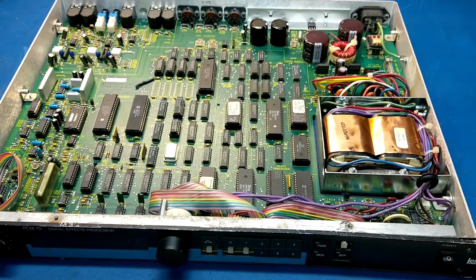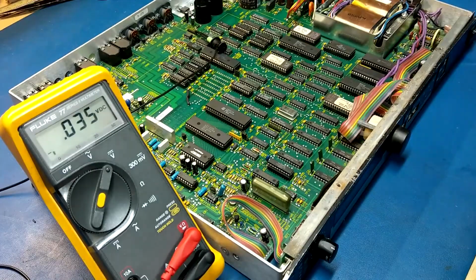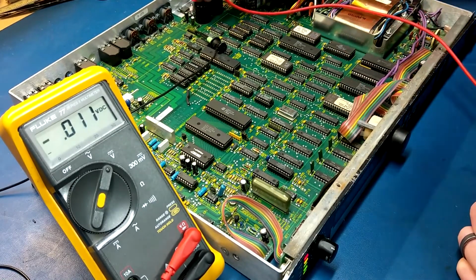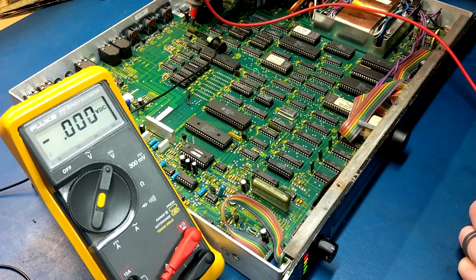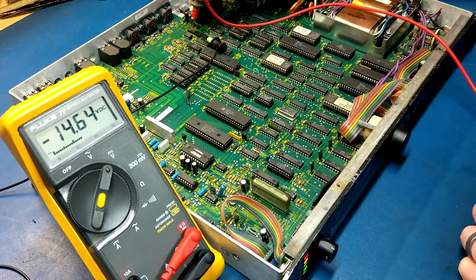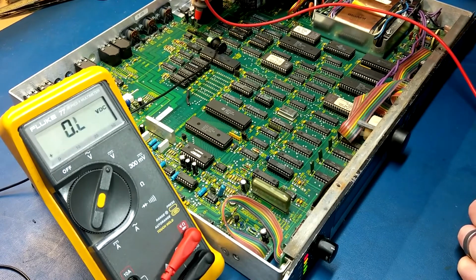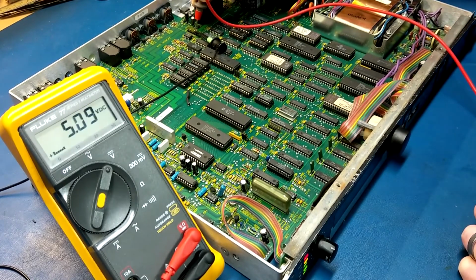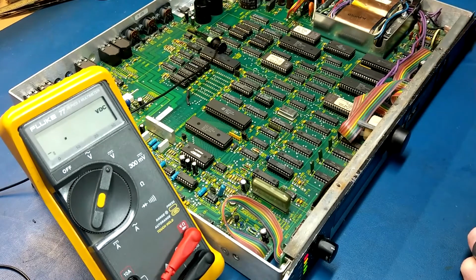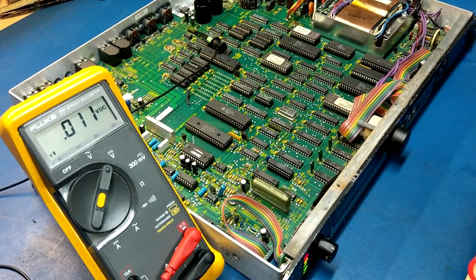If none of those are successful and everything is within tolerance, then we'll start looking at the data sheet for troubleshooting this guy. Alright, checking voltages is the next step. So we'll be looking at the taps back here. And starting with plus 15, we look good. We'll go minus 15. A little low, but we're good. And then plus 5. 5.09. So we're good. Power supply voltages there are good.